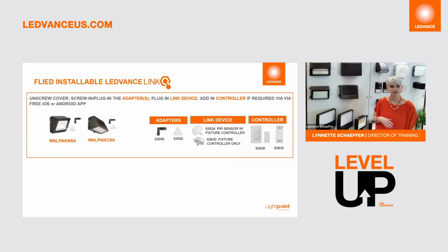Next up, we have the ability to add Link. Now, Link is our network lighting controls. Similarly, you unscrew the cover, screw in the bracket. We do have another little adapter that you do need to be able to add your Link device, whether that's the fixture controller or the fixture controller with sensor. What's nice about our Link system is that you can easily group luminaires. You can set your maximum brightness, also known as high-end trim. You can do some basic scheduling and customize the sensors and many other settings within the LEDVANCE Link network lighting control app. The app is completely free. It is via iOS or Android.